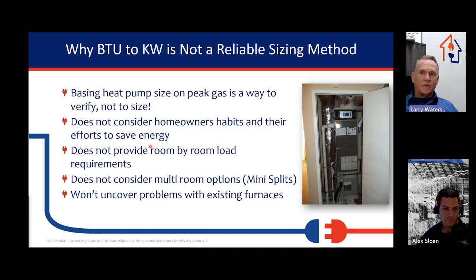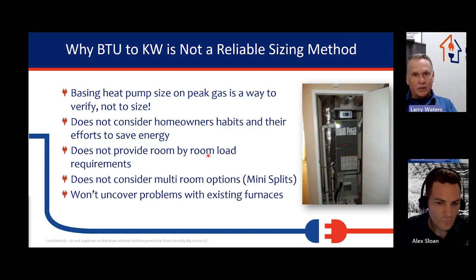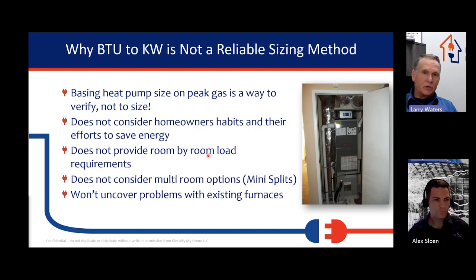It also does not provide room by room load requirements. It doesn't consider multiple room options like mini splits, and it won't ever uncover problems. So if you've got an old furnace and we're using peak BTUs, and it's got really old leaky ductwork, and they were just wasting a ton of energy but staying warm, if we size to that, we're going to put too large of a system in because of the inadequacies in the existing system. So it's a good way to kind of double check, but it's not a great way to size a heat pump. There's too many unanswered questions there.